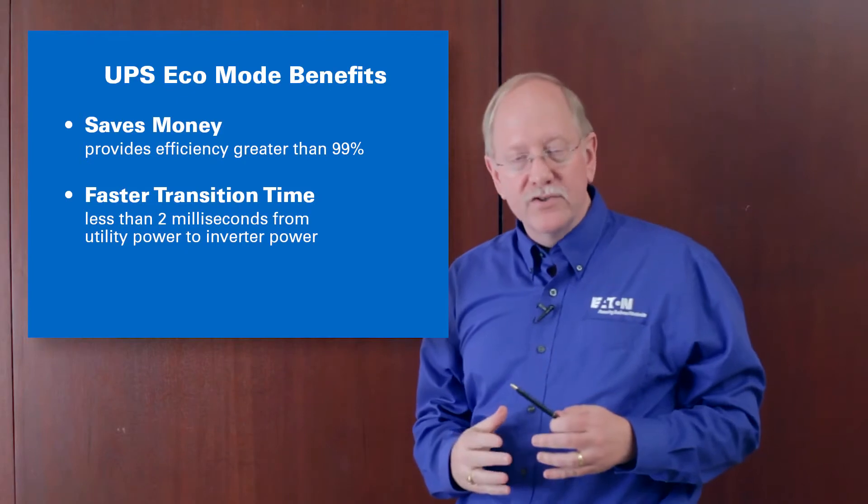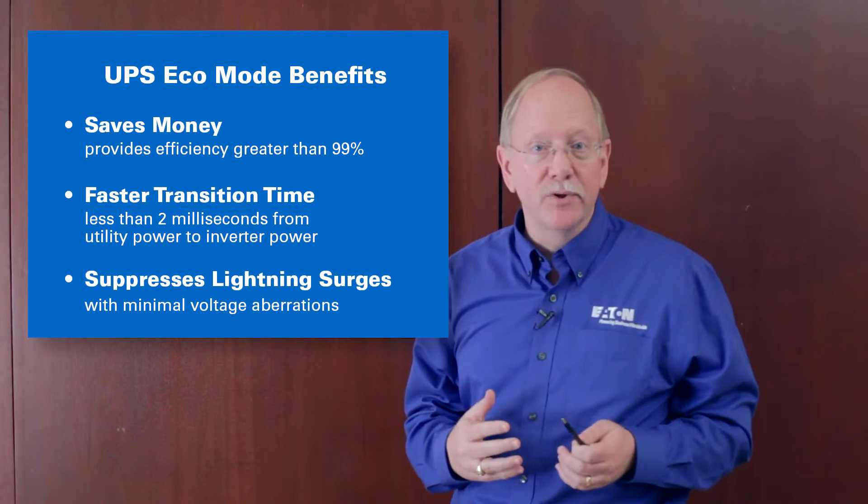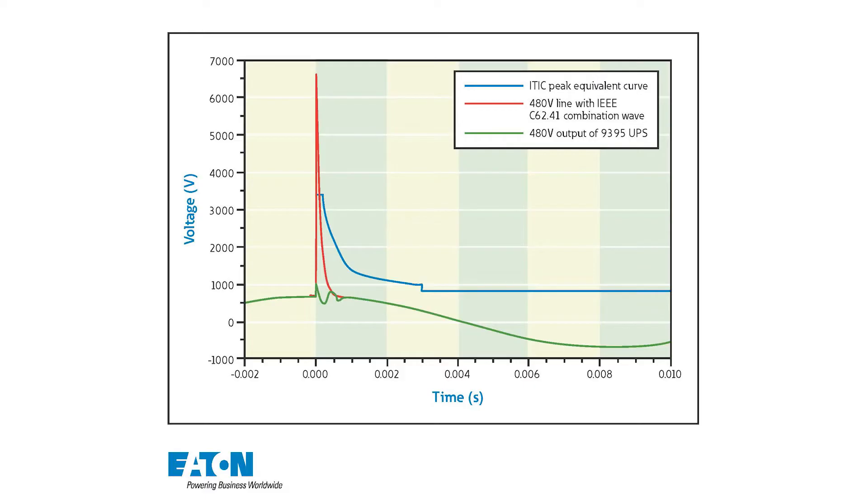One of the primary concerns with eco mode UPS operation is what if I have a disaster like a lightning strike on the input terminals of the UPS. So this graphic shows how that would look. I have a 6,500 volt very narrow spike here on the input of the UPS in eco mode but the green line here shows only a small voltage aberration at the output of the UPS.